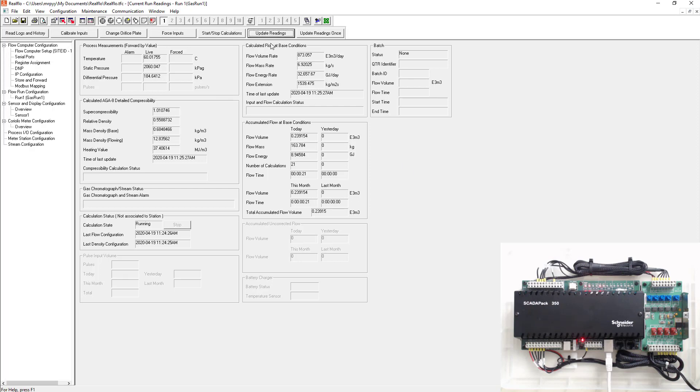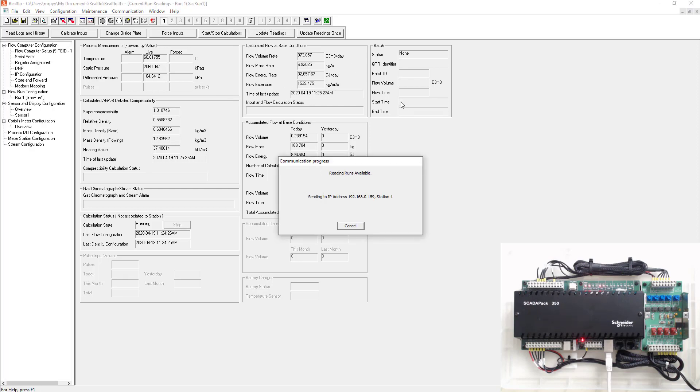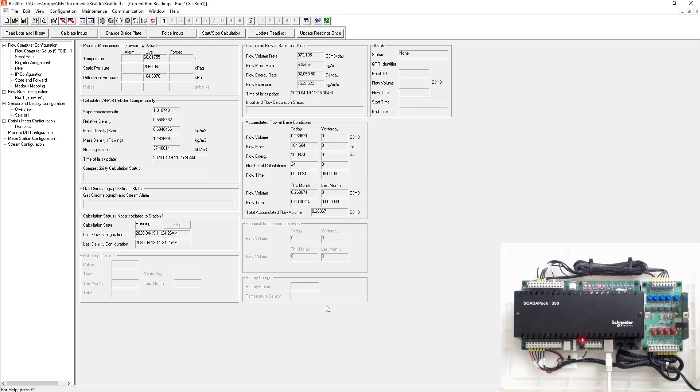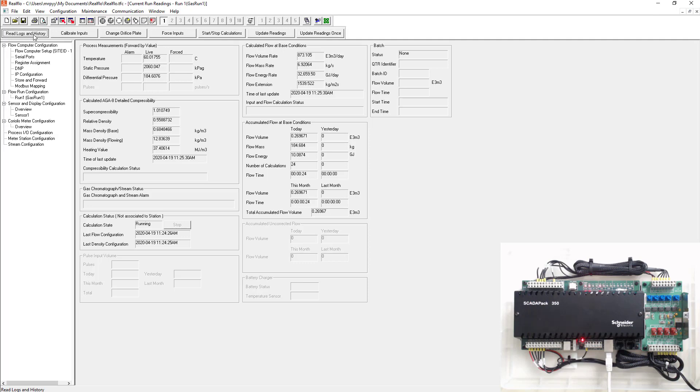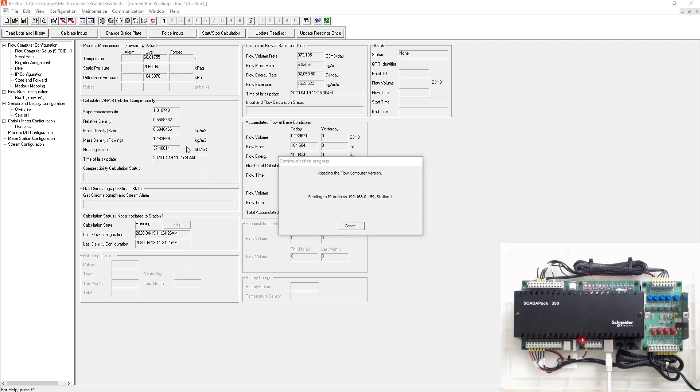You could also hit the update readings once. It'll take a snapshot of everything at the same time. You could go and put this into your flow calculation software that whether that's flow check or whatever it might be. As well as you can start and stop the calculations for the inputs, change the orifice plate, calibrate the inputs from here. We're going to go ahead and read the logs in history. When I do that, we're going to read everything.